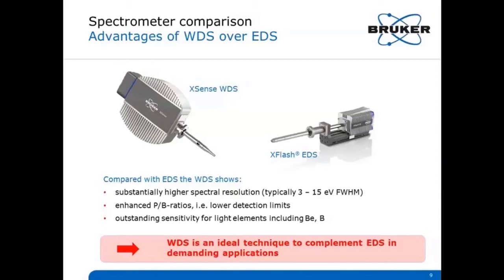And third, this is a special property of the parallel beam spectrometer with the grazing incidence optic: outstanding light element sensitivity. With these properties, a WDS can be an ideal complement to an EDS system in demanding applications where EDS peak overlaps are an issue, when trace element or light element detection capabilities play an important role, or for low kV applications if high spatial resolutions are desired.